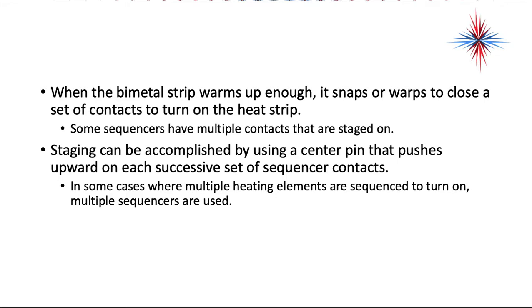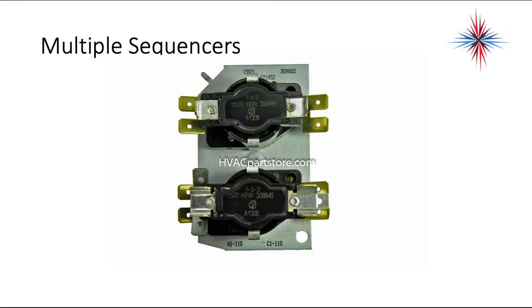In some cases where multiple heating elements are sequenced to turn on, multiple sequencers are used. This is an example of a multiple sequencer. We have a stage 1 that turns on our first stage and our blower motor. Once that is operational, the second sequencer will come on, and about 120 seconds later, the second stage of heat would come on.